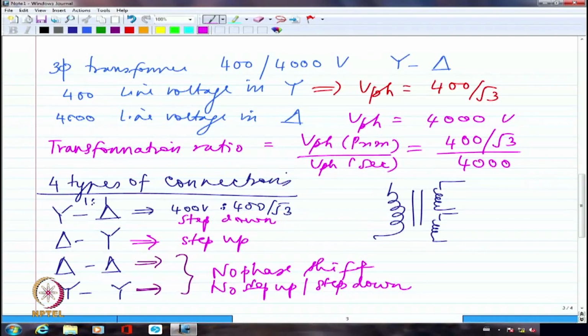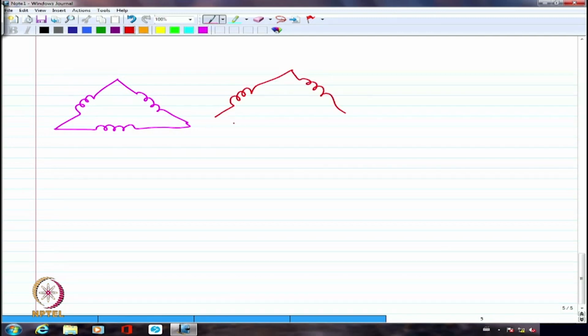Delta-delta configuration, one major advantage we have is that if one of the single phase transformers conks out, we will still be able to operate it as an open delta or V configuration. What I mean is, let us say I have the three-phase transformer here in delta like this. Maybe this is my primary and this is my secondary. And let's say one of these has conked out for some reason. One phase has conked out. Maybe the transformer has been having some fault.